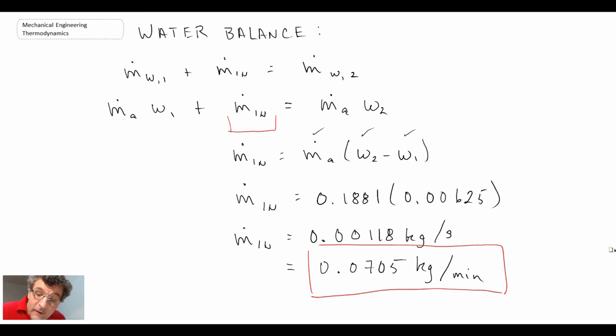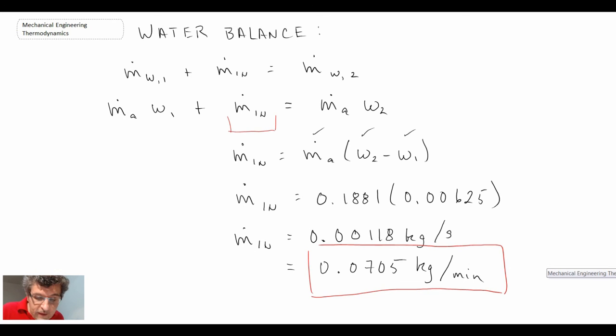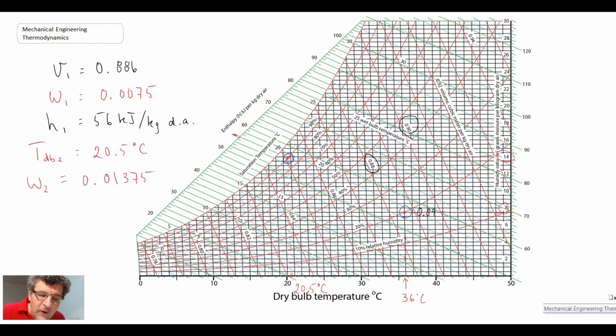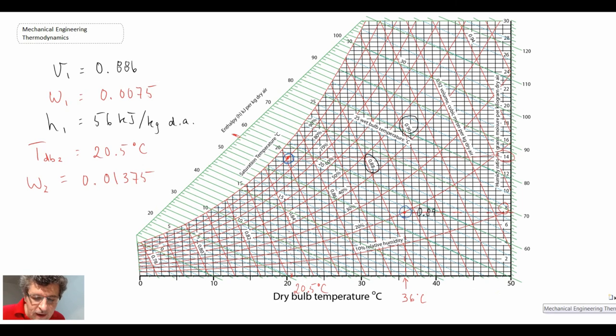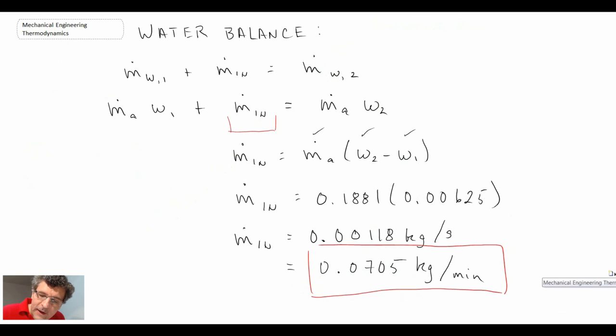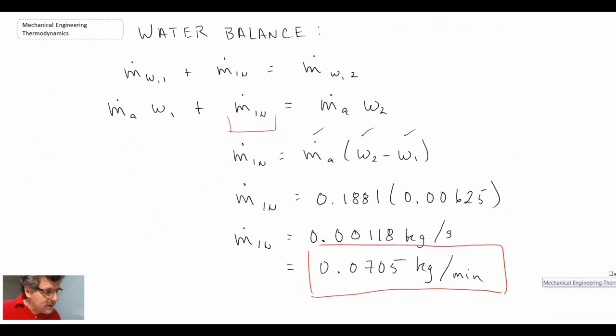This example shows cooling from 36°C down to 20.5°C while the relative humidity rises from 20% to 90%. Using the psychrometric chart is relatively simple and straightforward — a little busy, but easy to navigate once you know the different features. A ruler helps for more accurate readings, but it's a much quicker approach than the fully analytical method used in the previous problem. This concludes the lecture and the section on heating, ventilation, and air conditioning.